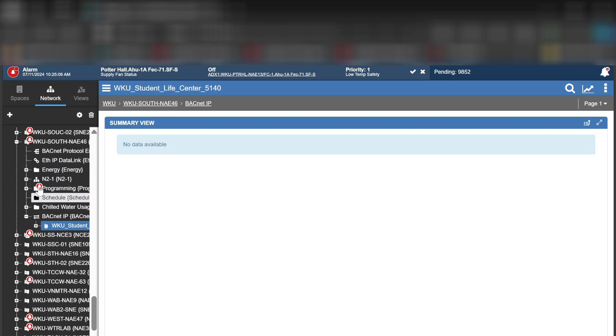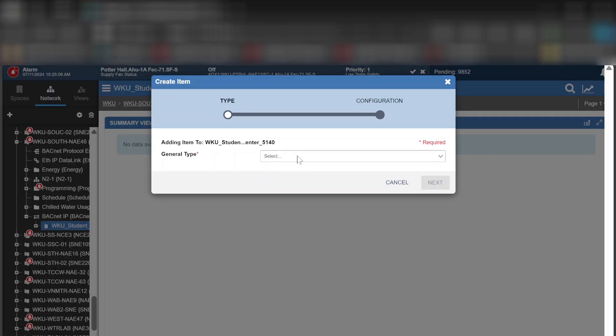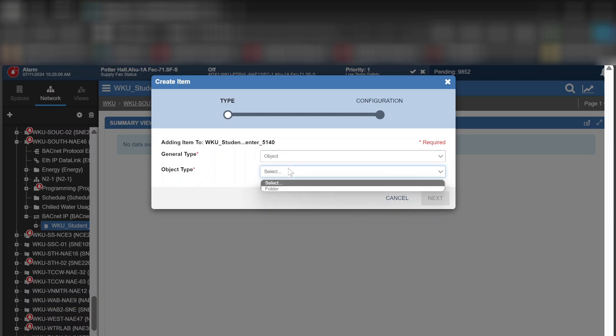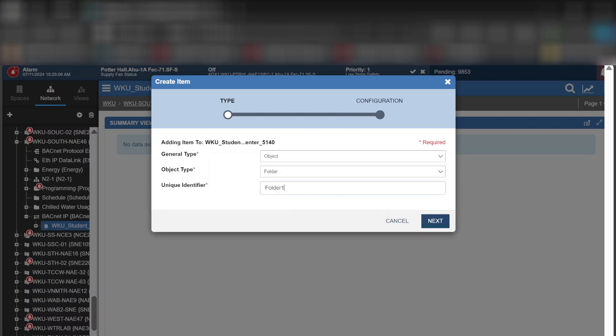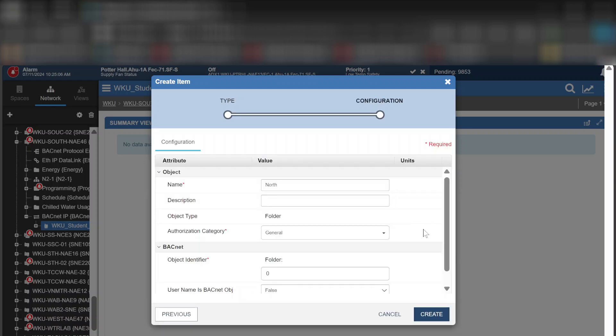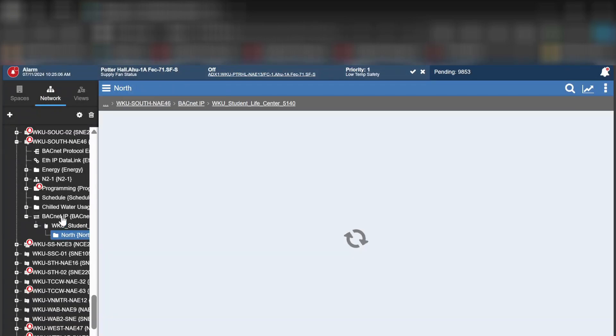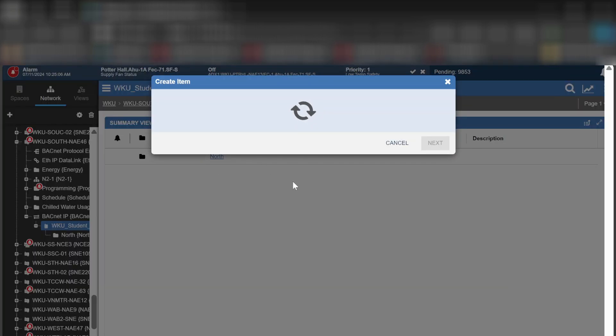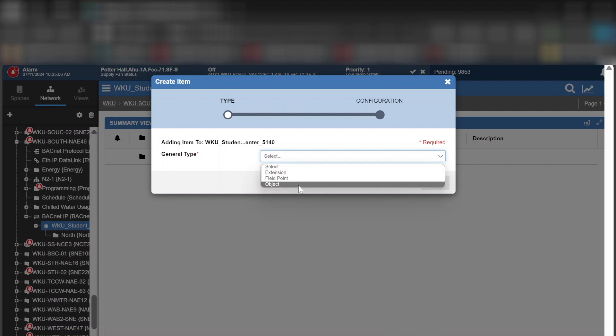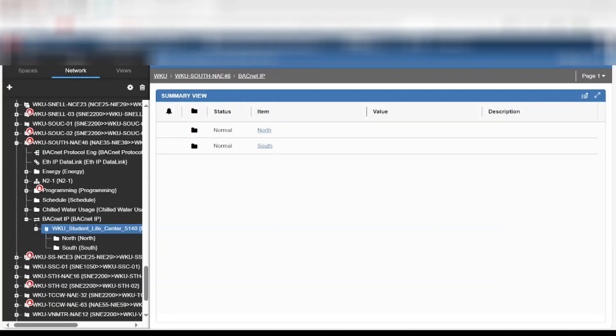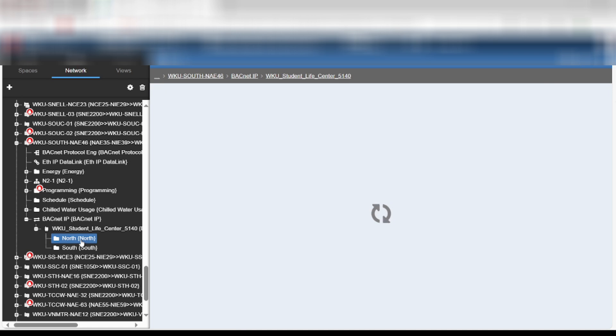Going in and adding folders, then pulling points into those folders, is a better way to keep things organized. I'm simply going to hit the plus sign, insert an object, and it will give me the option for a folder. Once I have that option, I'm going to name the folder something relevant to the group of points I'm going to be pulling in. If you don't take this step you're going to regret it later when you're trying to clean your system up — it makes your life much easier.